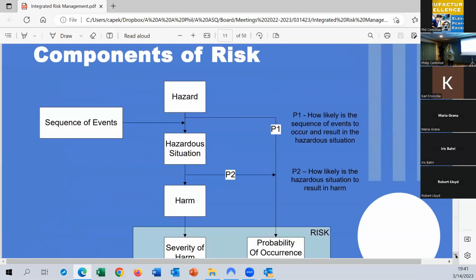This diagram appears in ISO 14971, and it shows the different components of risk. We start with a hazard, and that hazard will lead to a hazardous situation. That's when the user is exposed to that hazard. That hazardous situation can result in harm, and harm can have different severities. That can go from maybe just a little cut to death. It can have different severities of harm.